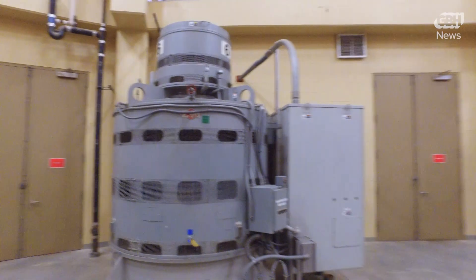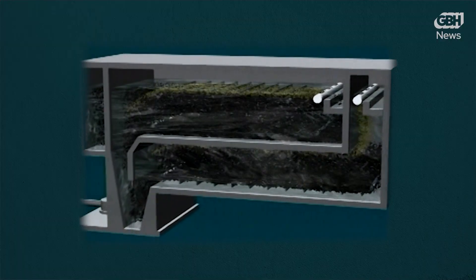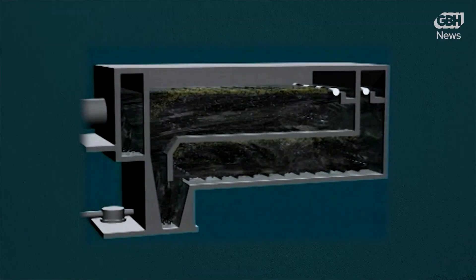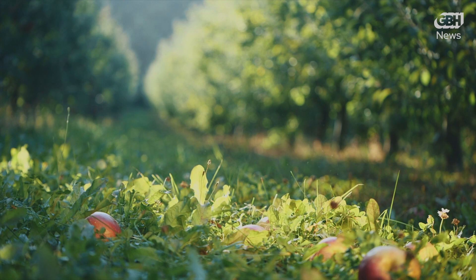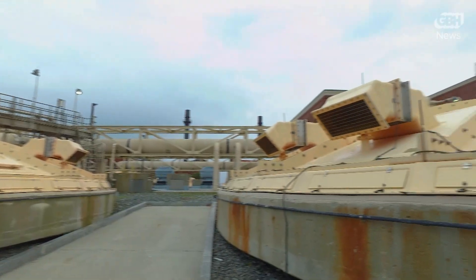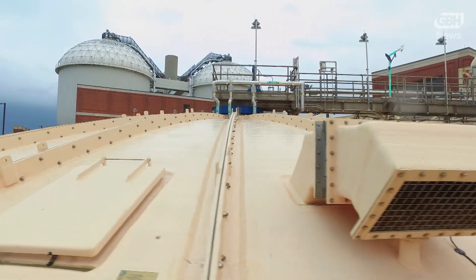You can actually see the pumps. If we stop pumping, it's going to back up into people's homes and businesses and flood them out. Once pumped, the water is slowed down so that solid material does settle. We collect that as residuals or sludge and treat it. It comes off the primary clarifiers at really dilute amounts, so we have to thicken it. For that, they turn to gravity, letting materials settle to the bottom in large, aptly named gravity thickeners until it's about the consistency of a Frappuccino. The excess water, now relatively free of solids, is pumped away.